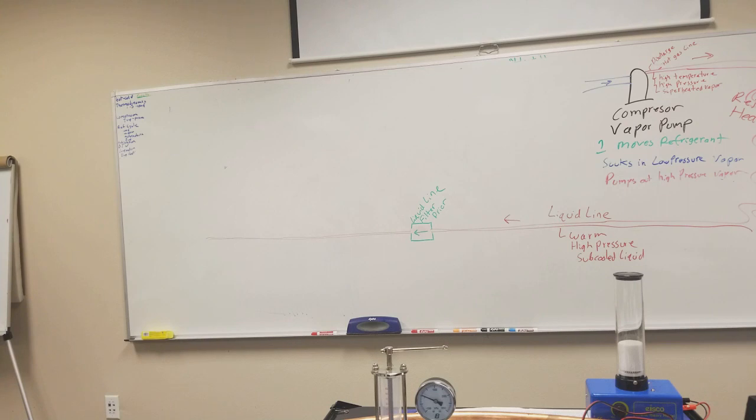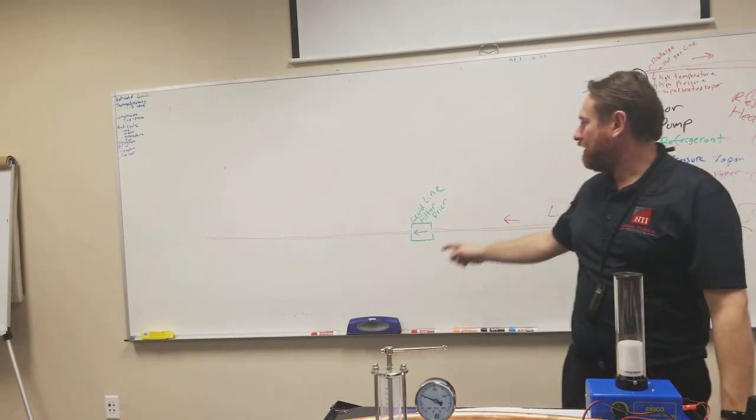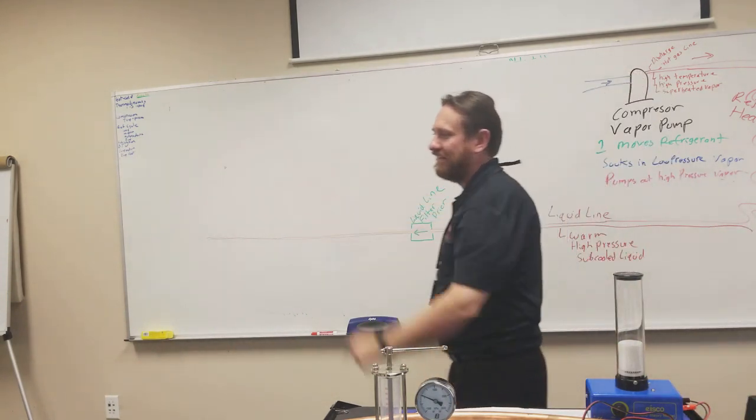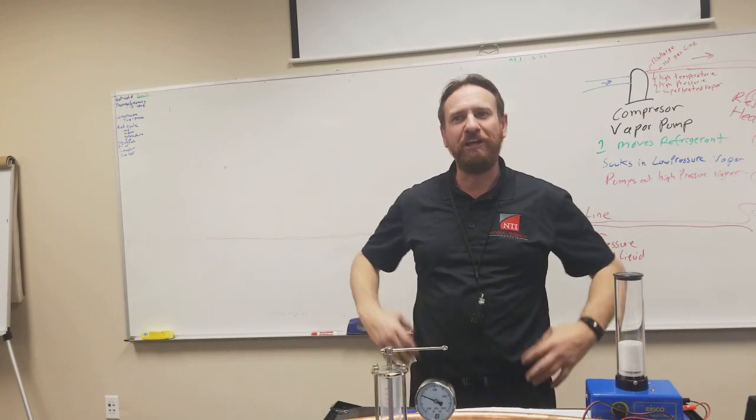So that is a liquid line filter and the dryer. You don't want to drop those. They make a lot of kinds, but two basic kinds. They make one that's a solid desiccant, like a rock like that, and they make another one that's made with BBs in it, and a spring holds them together.